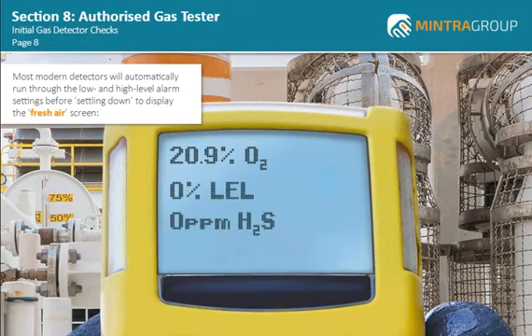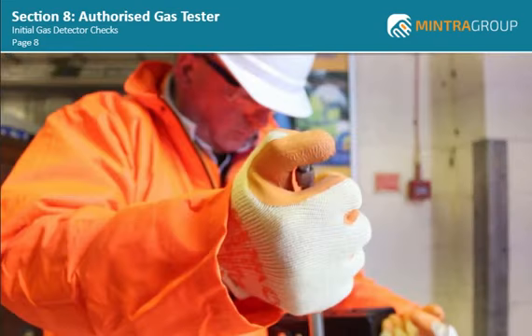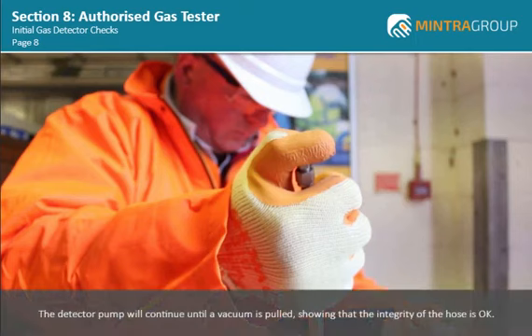Most modern detectors will automatically run through the low and high-level alarm settings before settling down to display the fresh air screen. 20.9% oxygen, 0% LEL, 0 ppm H2S, and 0 ppm carbon monoxide. You will now be asked to block the probe by placing your finger over the end nozzle. The detector pump will continue until a vacuum is pulled, showing that the integrity of the hose is okay.